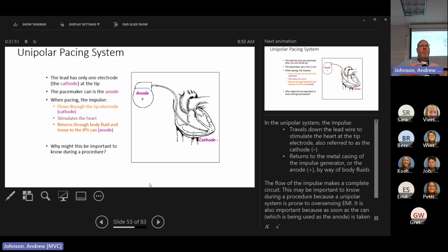The problem with doing unipolar pacing off just 1 wire is that if I'm sensing off of that, I can pick up a lot of noise on the outside. Pacemakers are sensing things, and environmental noise is a big issue. Whenever I'm sensing in this little area with an anode and a cathode close together, I don't have to worry as much about that environmental noise, like ICU noise.